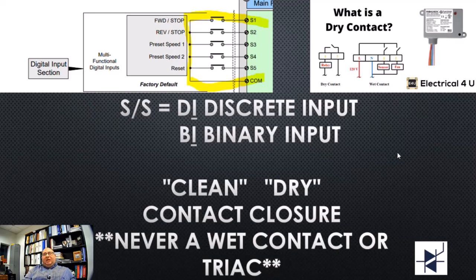The reason is this is a DC voltage signal generated by the VFD drive. It can't be shared with any other switches along here. It could not go on a triac. A triac is only for AC switching. Look at this, triac. Triacs are only used for AC, alternating current. And it cannot be used on a wet switch. Usually wet switches are triacs, but it cannot be used in this situation either.